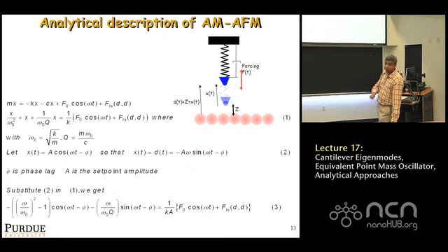Which means that phi is the phase lag. It's not the phase lead, it's the phase lag, okay? Very important distinction. You need to be very careful in your AFM analysis about whether your AFM system plots phase lead or phase lag, because interpretation flips depending on what you do. Here, I've defined phi as a phase lag because many AFM systems actually have it plotted as phase lag.